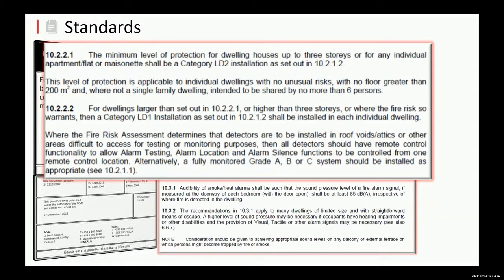And this is an interesting point. The next part is where the fire risk assessment determines that detectors shall be installed in the roof. So if we're going for an LD1 system, then a control switch should be installed on that system. Okay, so you need to allow for the functionality of alarm testing, alarm location, and alarm silence. Okay, so that's important from that point of view. So if you're installing in an attic space or in an area where you can't get to the test facility on the device itself from the ground area, whatever implement you're using, you have to use a control switch.